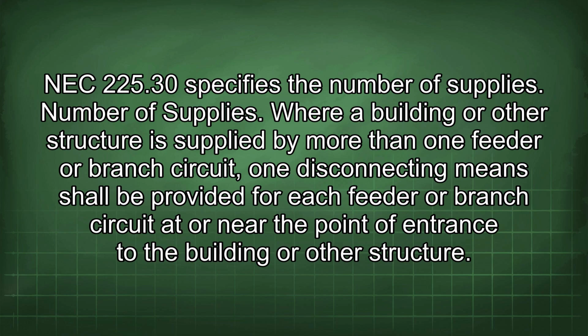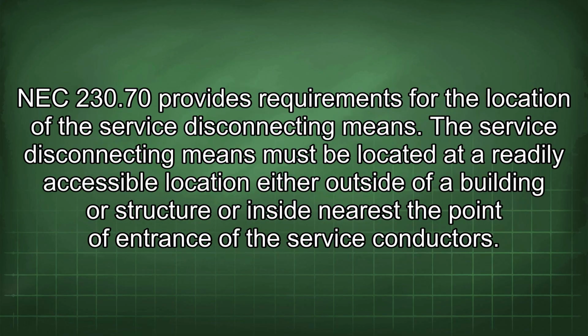Number of supplies. Where a building or other structure is supplied by more than one feeder or branch circuit, one disconnecting means shall be provided for each feeder or branch circuit at or near the point of entrance to the building or other structure. NEC 230.70 provides requirements for the location of the service disconnecting means. The service disconnecting means must be located at a readily accessible location either outside of a building or structure or inside nearest the point of entrance of the service conductors.